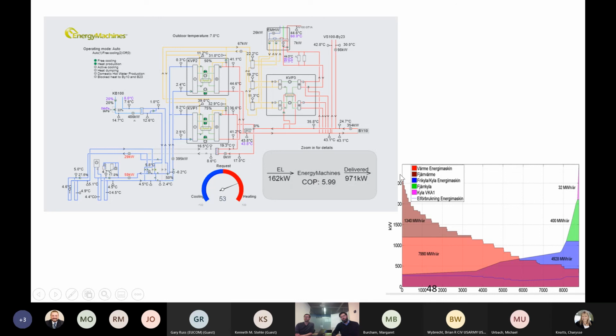Above here we use the district heating provided by the city for the peak load, and over here we have other heat pumps in the system configured as chillers that get rid of this energy. Today they are continuously expanding the heat pump part of this network to become completely self-sufficient. They even think they can drag so much energy out of the hospital that they could start supplying a neighboring low temperature grid to houses next to the hospital.